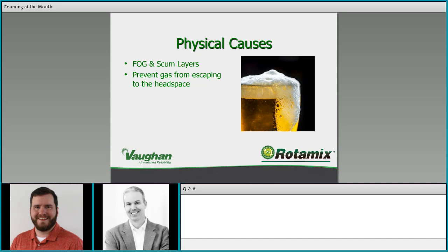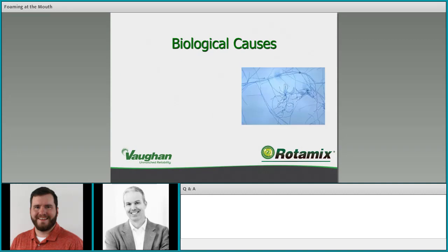FOG and scum layers are more rapid rise-type scenarios — they prevent gas from escaping to the headspace. If you have a very thick scum layer on the surface, gas can no longer pass through into the headspace; it builds up in the digester volume. This is most likely to cause a rapid rise or digester burping incident where gas builds up for a period of time, develops enough pressure to burst through the scum layer, and you see burping or sludge overflow — generally very dramatic, all-at-once type events.